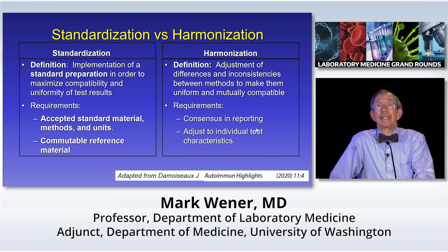So there are standards for standards, and the International Organization for Standardization, ISO, has this lab test traceability platform. I do get a kick out of the fact the name is International Organization of Standardization, which ought to be IOS, but here are standards, and they're calling themselves ISO. Nevertheless, they do define traceability to the highest available reference system component. The jargon here is, if you have a reference method or a certified reference material, use it, but sometimes that's not available. And so there are these calibration hierarchies. Diagnostic lab methods need to depend on what's available. And if you don't have these absolute gold standards, you use what you can.